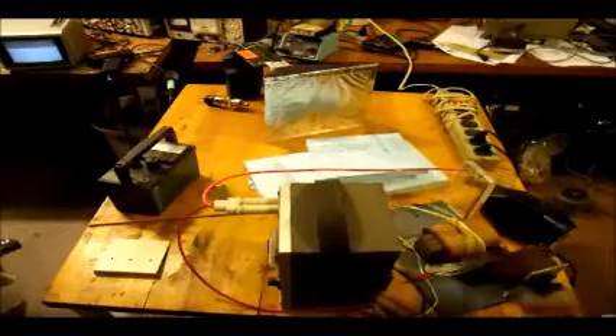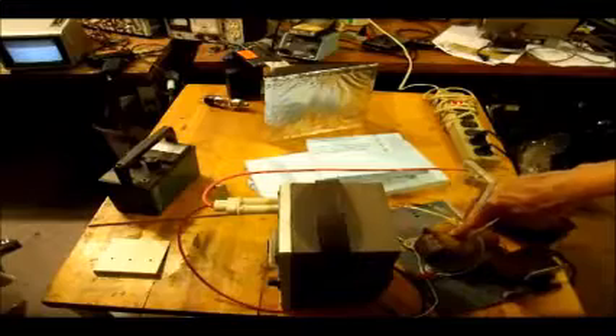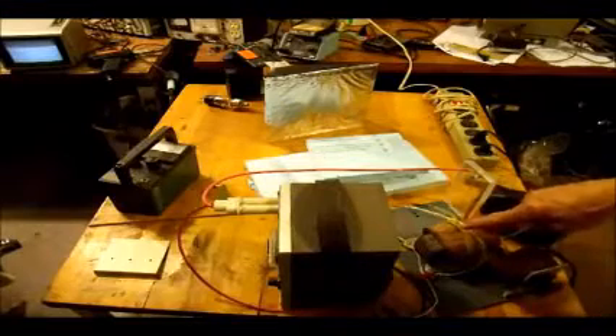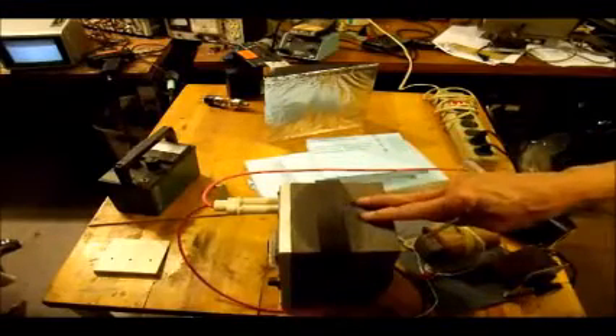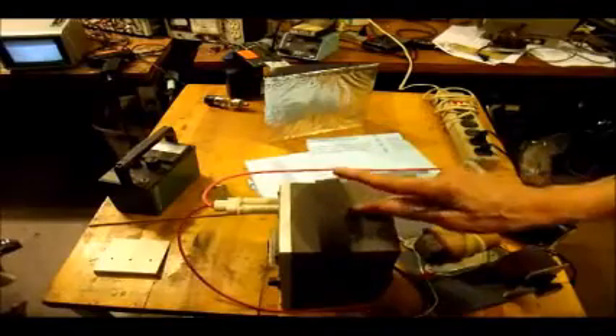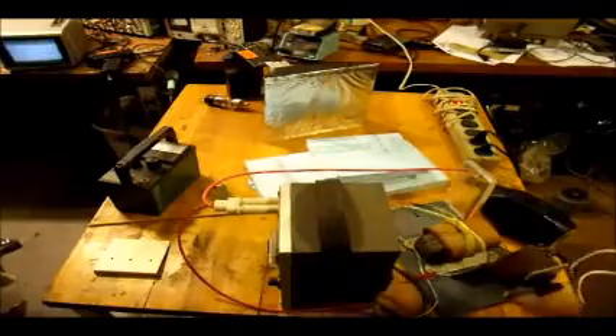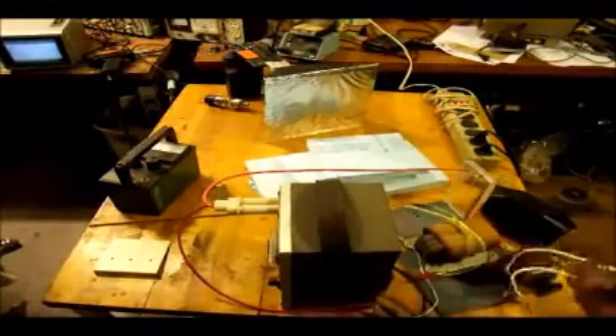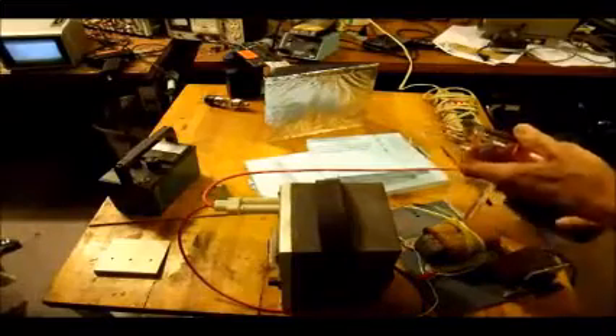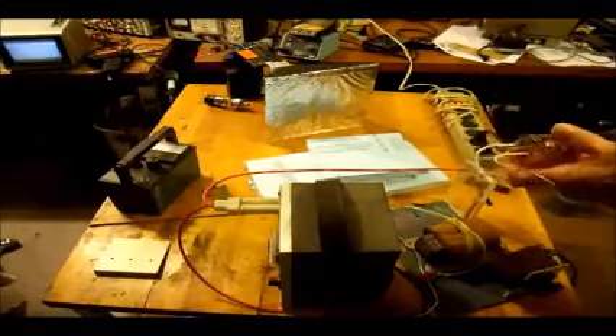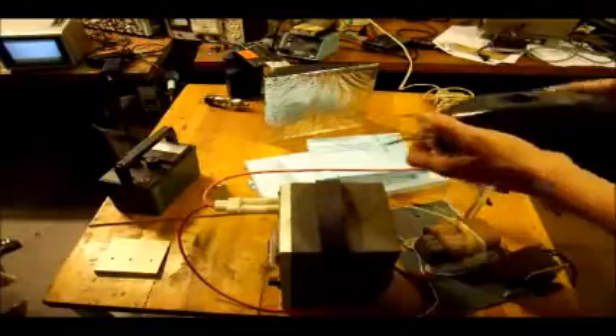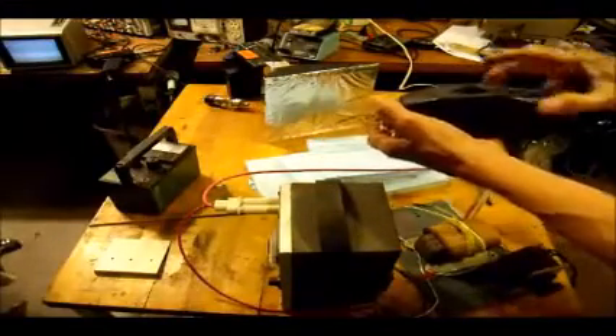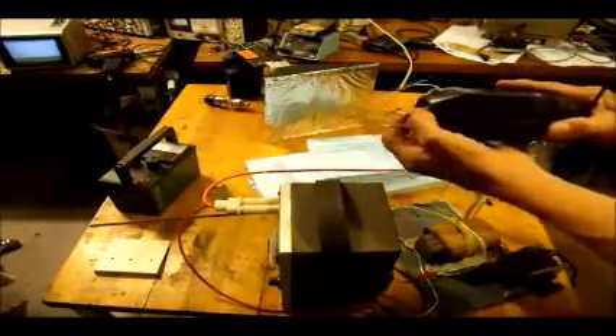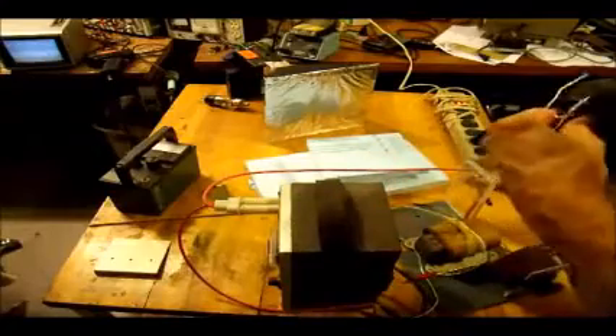This is our setup here. We have a filament transformer with a variac hooked onto it. We have a high voltage power supply. It goes from 10 kilovolts to 40 kilovolts. We've got a survey meter to make sure we don't get radiated. We've got a fluoroscope here, which is used to see the output of the tube. Okay, we'll go ahead and put the tube into the housing. This housing is made out of a lead-filled plastic, and it's used to get rid of all of the stray radiation.